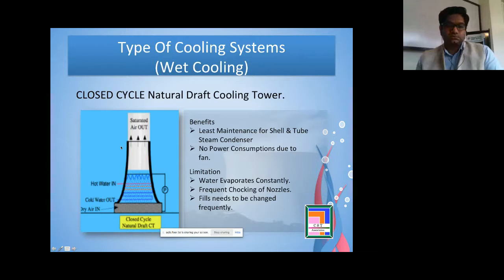And then we have the closed natural draft. In some cases I've seen in the world that they have used a fanless system, but as a closed one. The system is the same as the forced draft, and this is a natural draft. The benefit is least maintenance for the shell and tube steam condenser, and no power consumption due to fans. See, there is no fan, no power. Limitations are that water evaporates constantly, nozzles choke frequently, and fill needs to be changed frequently.